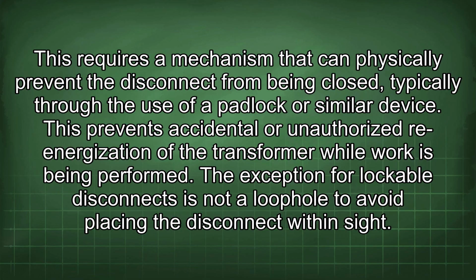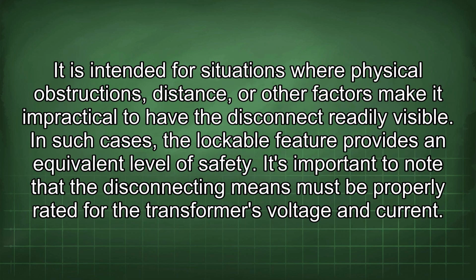The exception for a lockable disconnect is not a loophole to avoid placing the disconnect within sight. It is intended for situations where physical obstructions, distance, or other factors make it impractical to have the disconnect readily visible. In such cases, the lockable feature provides an equivalent level of safety.